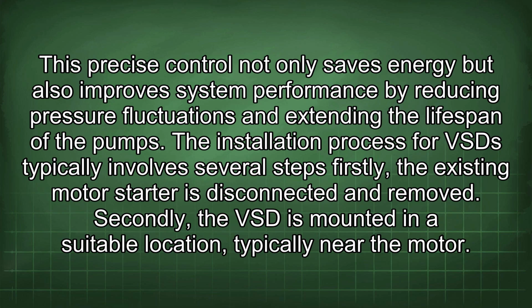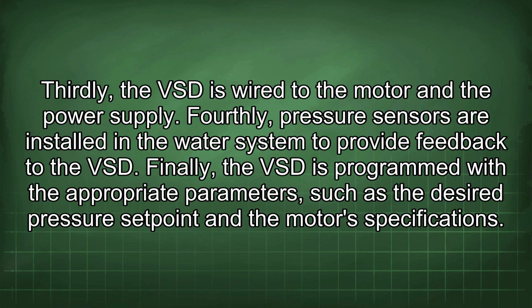Firstly, the existing motor starter is disconnected and removed. Secondly, the VSD is mounted in a suitable location, typically near the motor. Thirdly, the VSD is wired to the motor and the power supply. Fourthly, pressure sensors are installed in the water system to provide feedback to the VSD. Finally, the VSD is programmed with the appropriate parameters, such as the desired pressure set point and the motor's specifications.